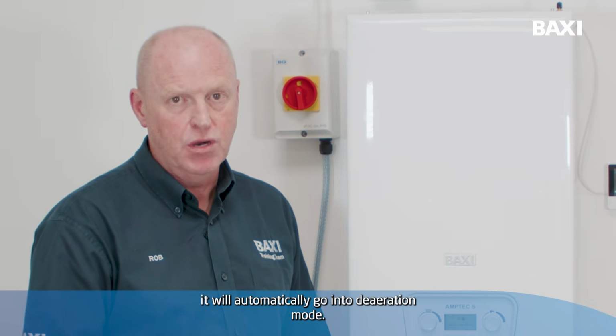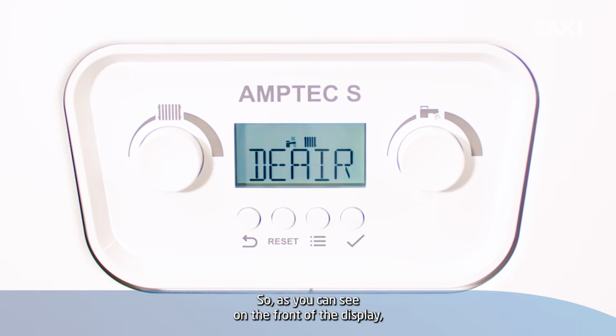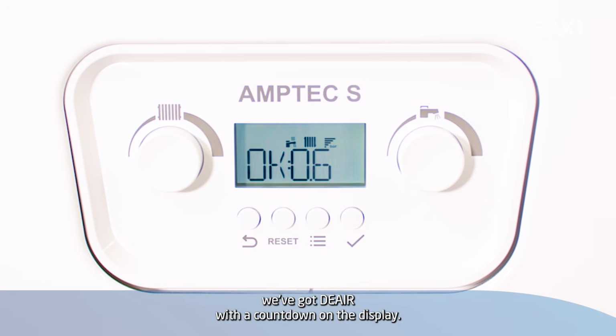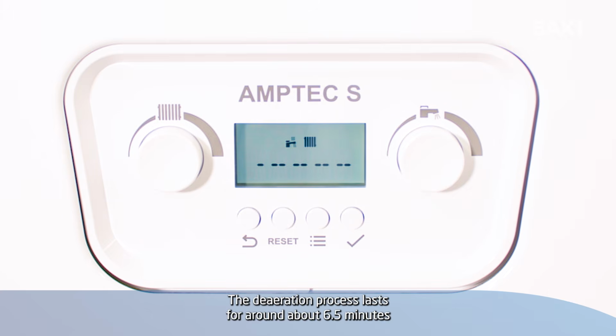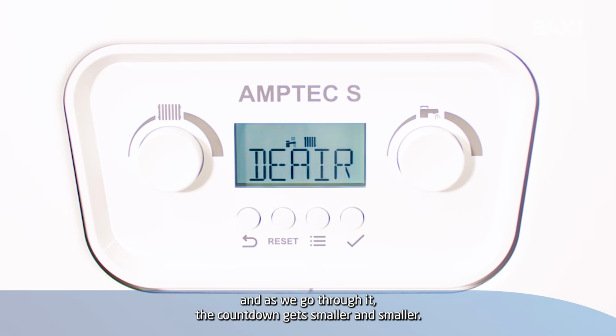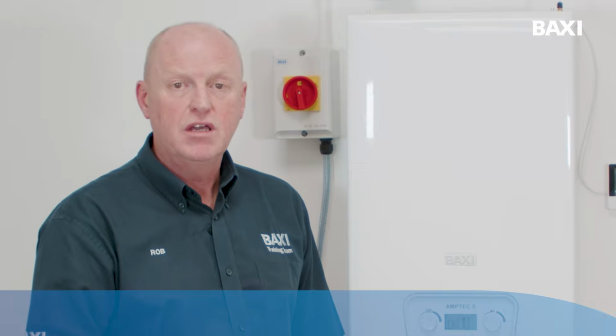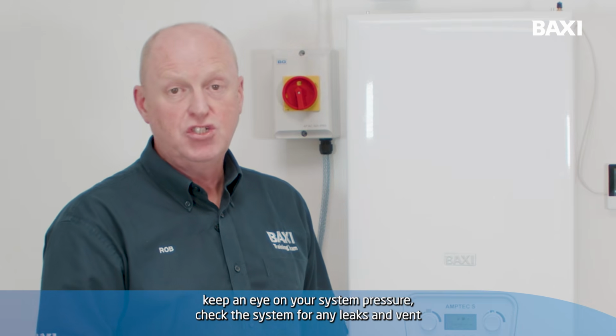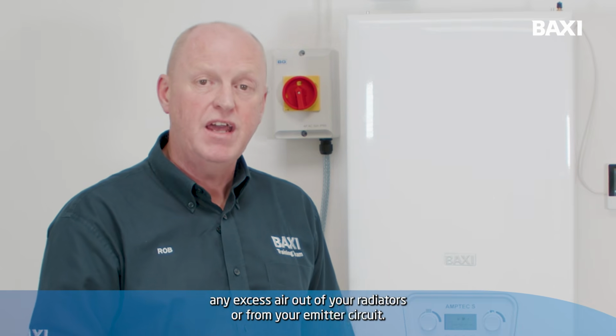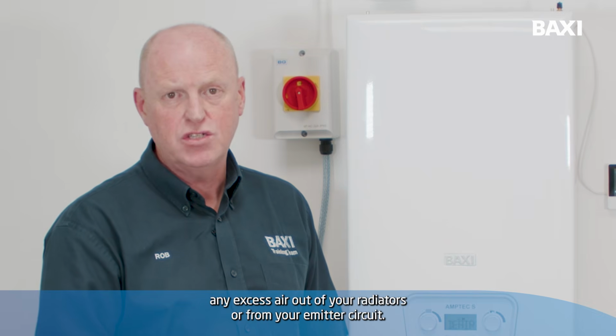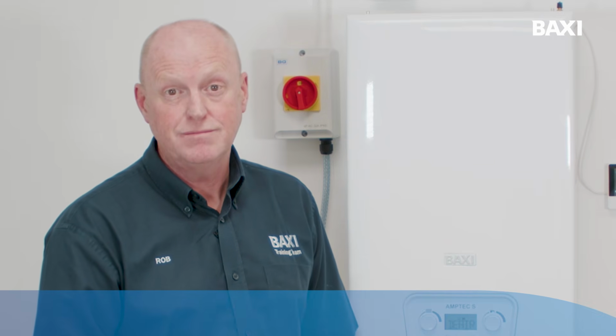into de-aeration mode. So as you can see on the front of the display, we've got de-air with a countdown on the display. The de-aeration process lasts for around about 6.5 minutes. And as we go through it, the countdown gets smaller and smaller. Now, what I recommend that you do is while it's doing the de-aeration, keep an eye on your system pressure, check the system for any leaks and vent any excess air out of your radiators or from your emitter circuit.